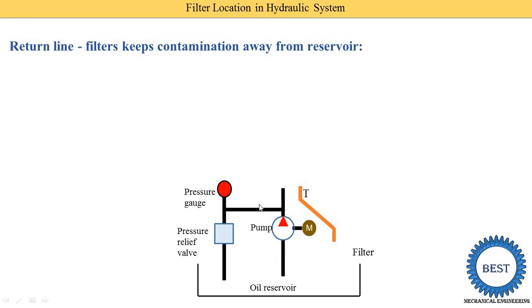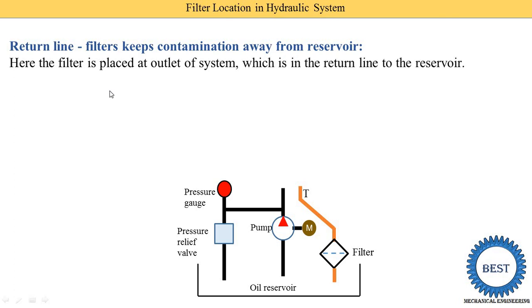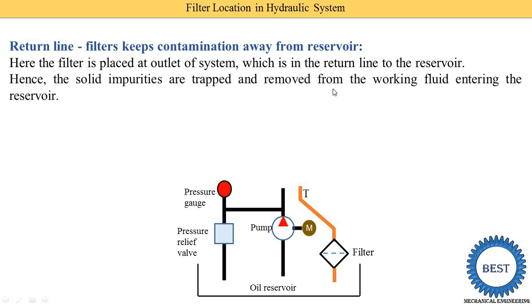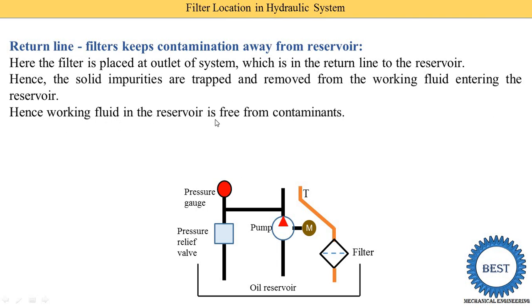Here you can see the oil reservoir, pump, and pressure gauge. The outlet of the pump is connected with a directional control valve and actuators. Oil returned from the actuators comes back into the directional control valve, and from there through a tank port back to the tank. The filter is placed on this return line before the oil reaches the reservoir. Solid impurities are trapped and removed from the working fluid before entering the reservoir, so the working fluid in the reservoir is kept free from contamination.